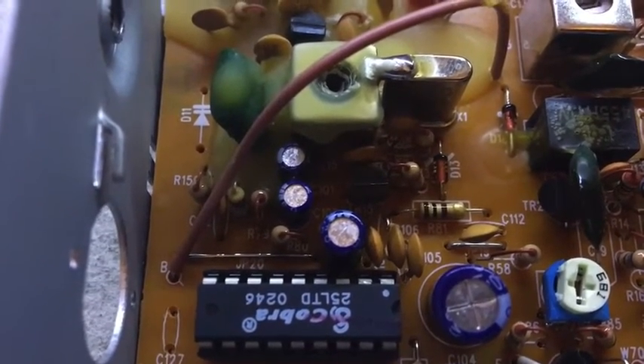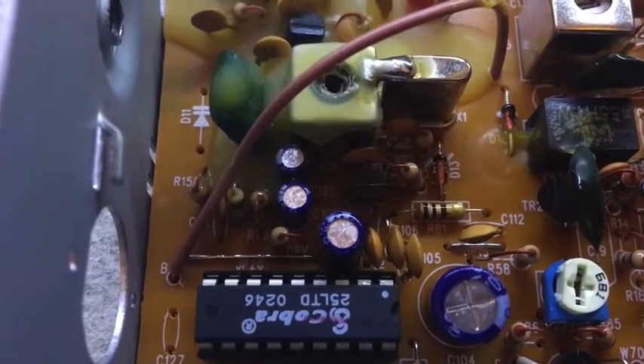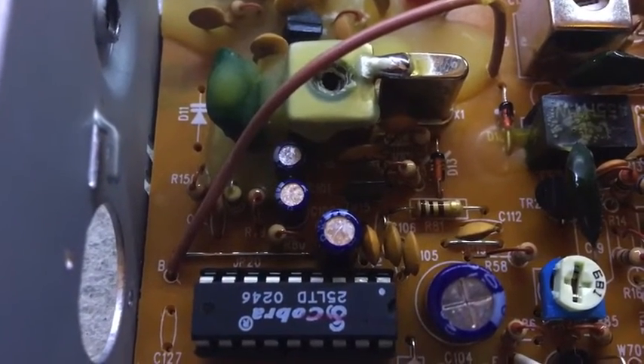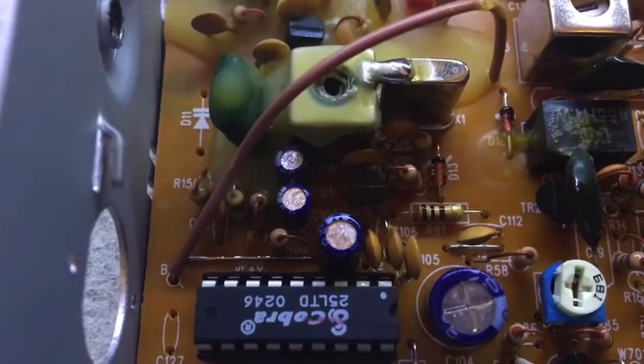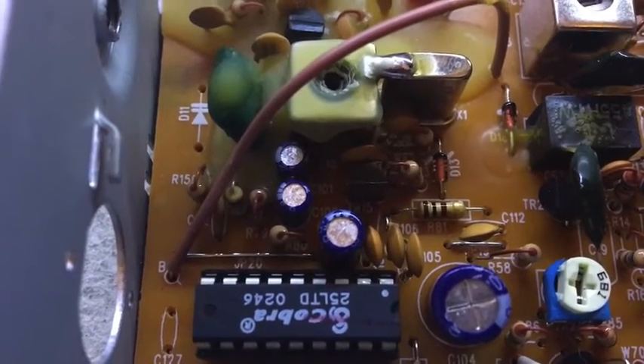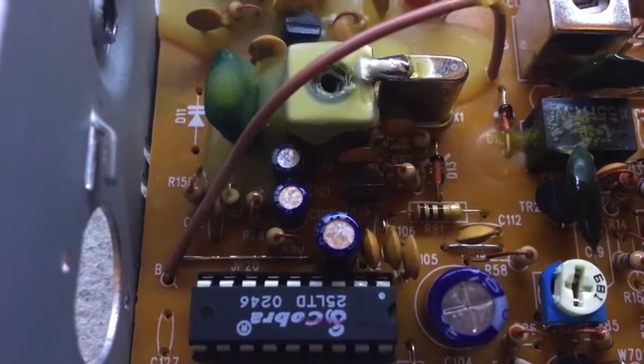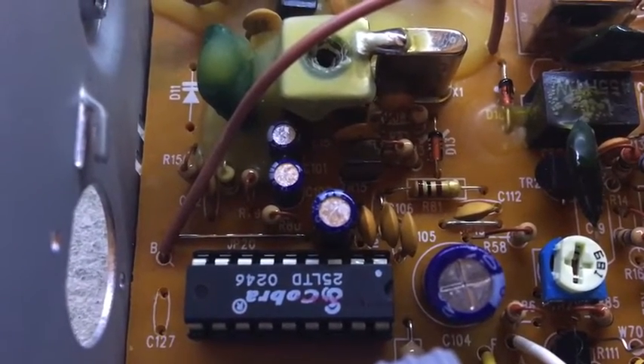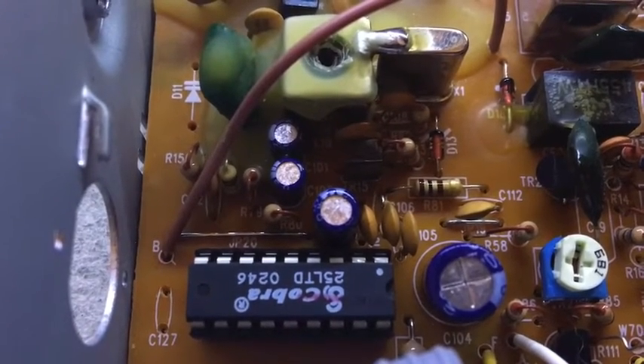Sometimes they do fail, like if a diode fails completely, you can't adjust the voltage. Well, you can't adjust the frequency by voltage, it just doesn't do anything. So that proves the VCO diode was okay.